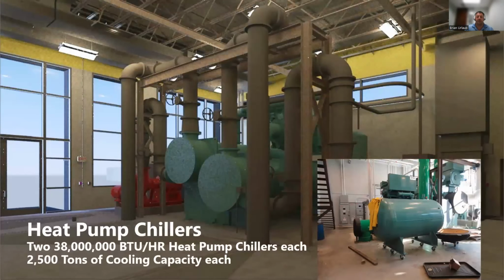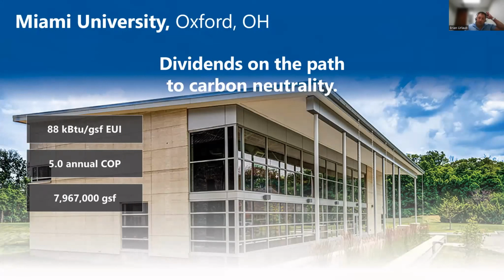These are just a couple of the chillers that are installed there on site. Miami University in Oxford, Ohio is another project that was recently completed. They're on their fourth phase of completion, with a total of 4 phases for the entire campus. And their campus is even getting better results than Ball State, primarily because with this particular system, we went with smaller chillers, more modularized, to be able to get better turn down, which increases your overall efficiency of the system. And there are 4 central energy plants here instead of 2. So again, going a little bit smaller, but that was primarily due to phasing and getting all this constructed without disrupting the entire campus at one time.